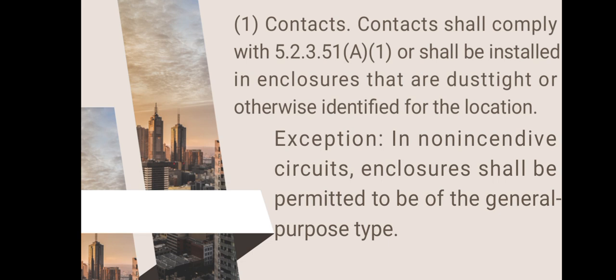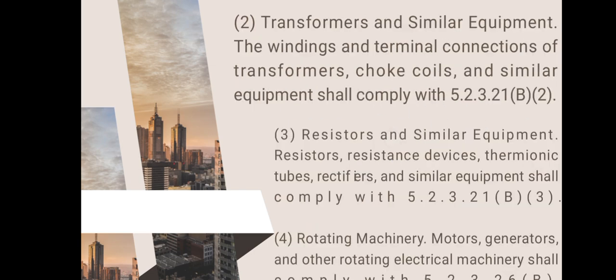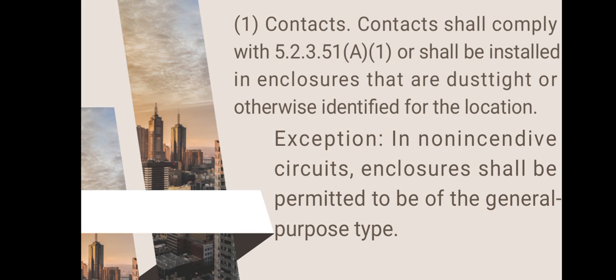For the switches, circuit breakers, motor controllers, and fuses, they must have enclosures. The enclosures must be dust-tight or otherwise identified for the location. Control transformers and resistors: switching mechanisms must have dust-tight enclosures. Coils and windings must have dust-tight enclosures. Resistors must have dust-ignition-proof enclosures. For the motors and generators, they must be totally enclosed non-ventilated, totally enclosed pipe ventilated, or dust-ignition-proof. For the luminaires, portable lighting equipment must be identified for the location. Fixed lighting must have dust-tight enclosures or be marked with maximum lamp wattage.